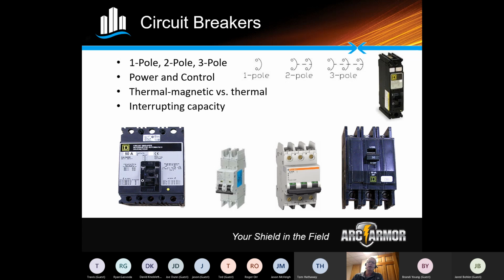And that's why there is also the thermomagnetic. So the magnetic side of that is more for short circuit or instantaneous overcurrent or inrush coming in when you start a pump. So if you think of the magnetic part being an iron core, just like a magnet with a wire wrapped around it, as the current flows through that magnetic core, it also generates a magnetic field which then would open up the breaker as well. So thermal is more for just overcurrent. Magnetic is really for instantaneous. So that's how I kind of keep the two together, and that's why most of the breakers that we see are thermomagnetic and not just thermal. So it provides 2 forms of protection to protect the conductors and anything downstream of that. Any questions on that? Comments?